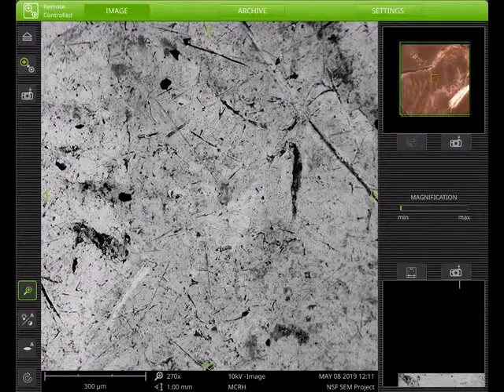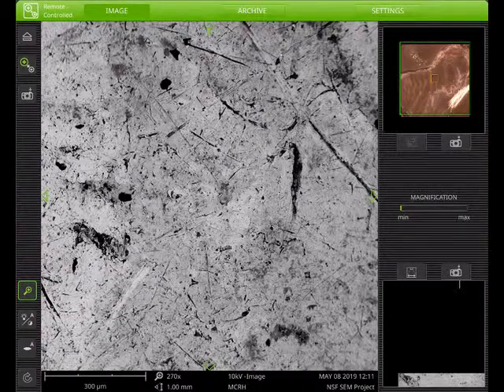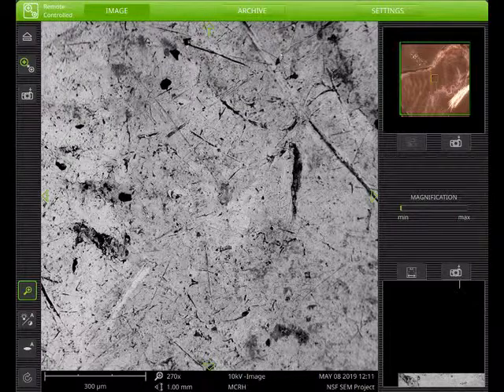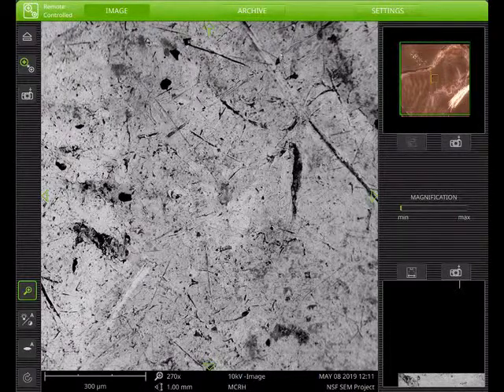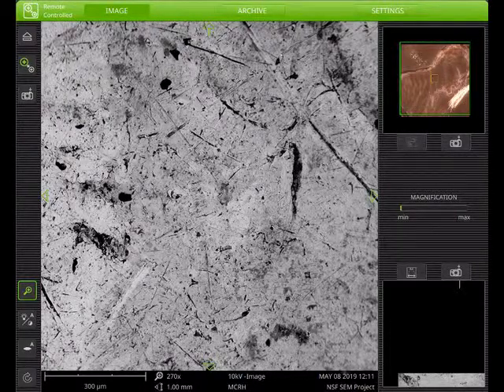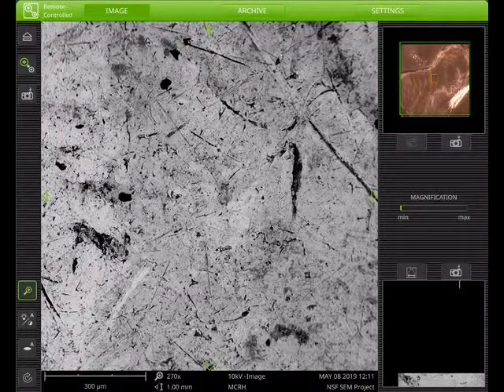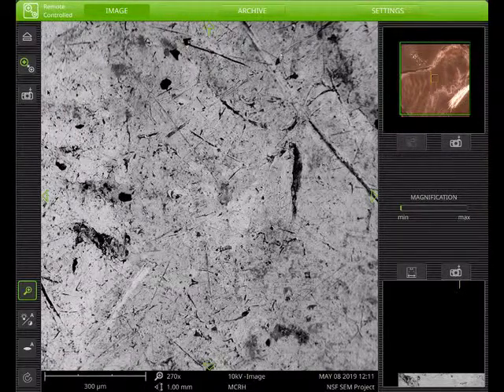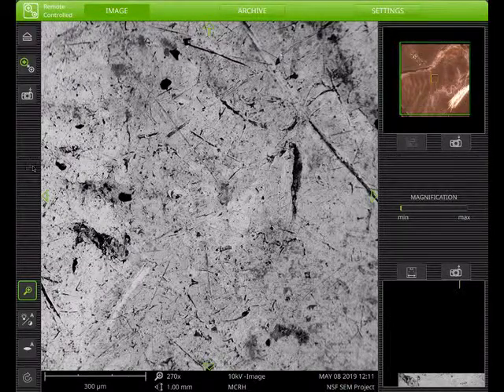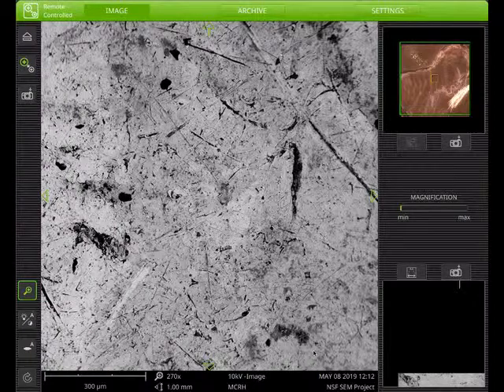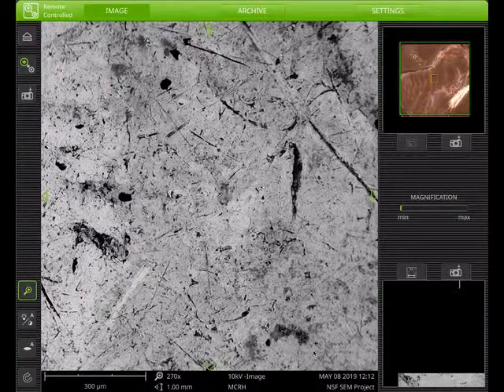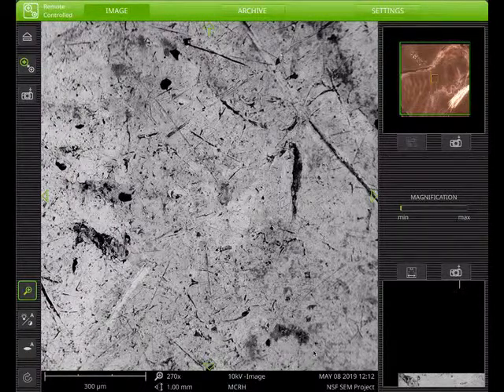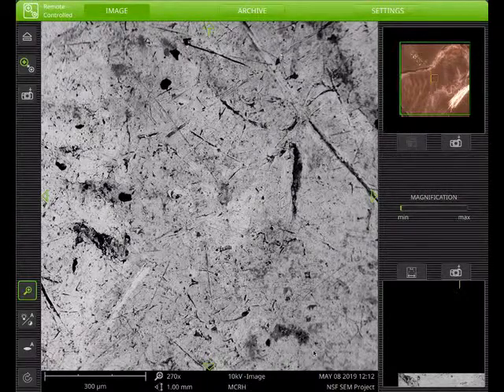In a minute we're going to look at how we can do a chemical analysis on the penny, but at the moment, what you're seeing is a surface, and you're seeing slight chemical differences between one part and another. The electrons come down, strike the surface of the penny, and move back up to the detector. So certain areas with low average atomic densities don't reflect electrons very well and they appear dark. Other areas are very bright because they're doing a more efficient job of reflecting or backscattering those electrons upwards to the detector.